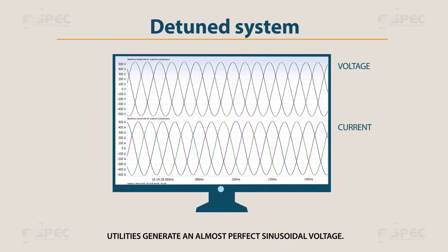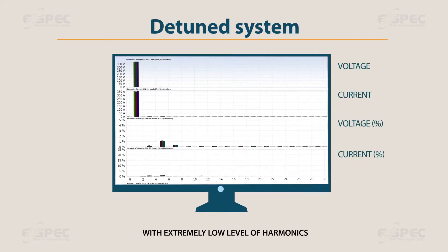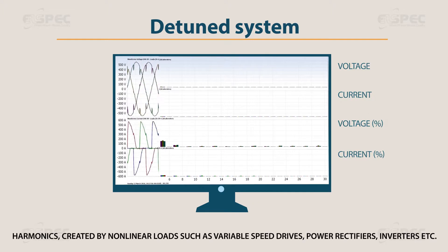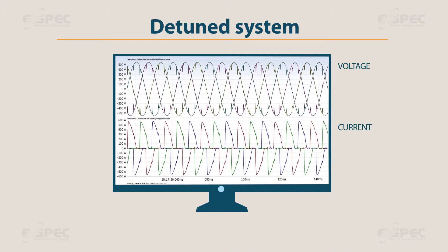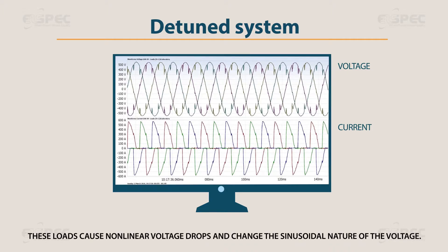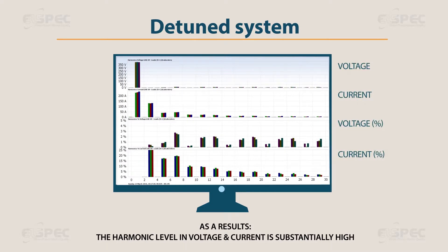Utilities generate an almost perfect sinusoidal voltage with an extremely low level of harmonics. Harmonics created by non-linear loads such as variable speed drives, power rectifiers, inverters, etc., cause non-linear voltage drops and change the sinusoidal nature of the voltage. As a result, the harmonic level in voltage and current is substantially high.